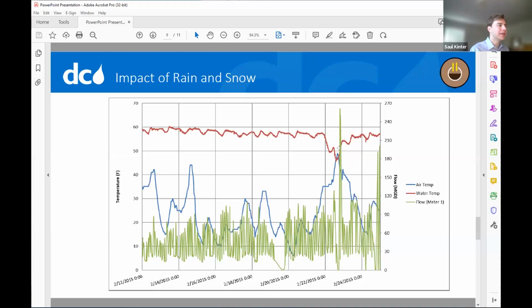The last point is that when this happens, by definition, we are not at peak heating load for the building, because the outside air temperature is in the 40s, if not up to 50 degrees. So when we see a drop off in the available sewer temperature, we aren't needing as much out of the system as it may have been designed to produce, because we needed that 3 days earlier when the temperature was down below 10 degrees Fahrenheit. At that point, the wastewater temperature was up in the 50s.